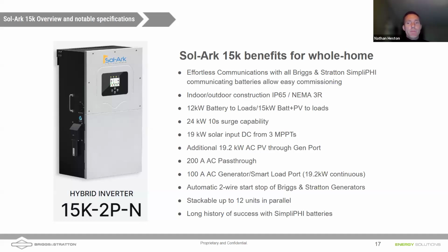It can continuously produce 15 kilowatts from that solar. Typically, you can oversize your solar array, so you're getting longer hours of full production and covering all your loads that way. 200 amps of pass-through, 100 amp fused connection on the smart load port. But that is derated down to 80 amps for continuous power pass-through. Same for AC coupled solar. You can do 80 amps continuous.